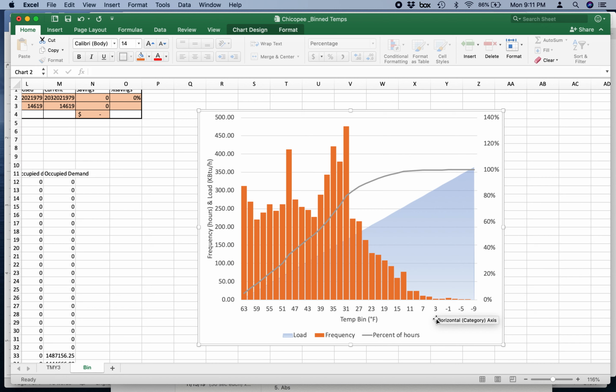And so the building load, this is a simplified building load because we haven't looked at occupancy yet, but as you can see, this spot over here with 100% of the load is actually colder than the design point. And what you can see is that never happens. That happens pretty much 0% of the time. And yet that's the temperature for which we're designing the heating systems.